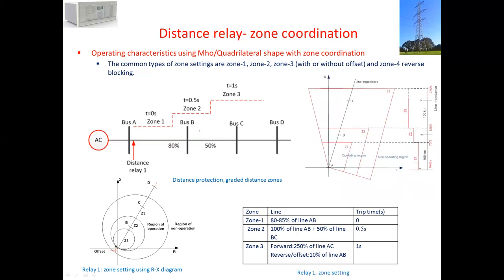Another shape is using quadrilateral characteristics. This is a better option for resistive coverage because it can go a bit down on the R section, more resistive. Zone 2, for example, if we use this one, it goes down slightly here. But with Mho, it doesn't go that much. This is the shape now. Zone 1, zone 2, zone 3 have the same application.